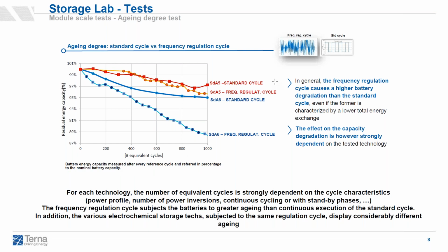So as expected, we can see that the frequency regulation cycles are more stressful for both ESS, even if we can see that for SDA5, there is a small difference in terms of reduction of energy capacity, while this difference is bigger for SDA6. So it means that SDA6 has been more degraded by the frequency regulation cycle. So we can conclude that, for example, the lithium technology of SDA5 is better for fast frequency application than SDA6.